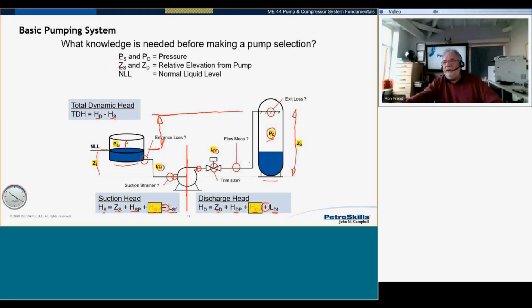But don't forget all the other stuff. Have you got a suction strainer there? You're going to lose energy as the liquid goes through the suction strainer. You're going to get a pressure drop. You've got a flow meter there, an orifice plate. You're going to have more friction losses and so on. Even exit losses going into this vessel at the end.